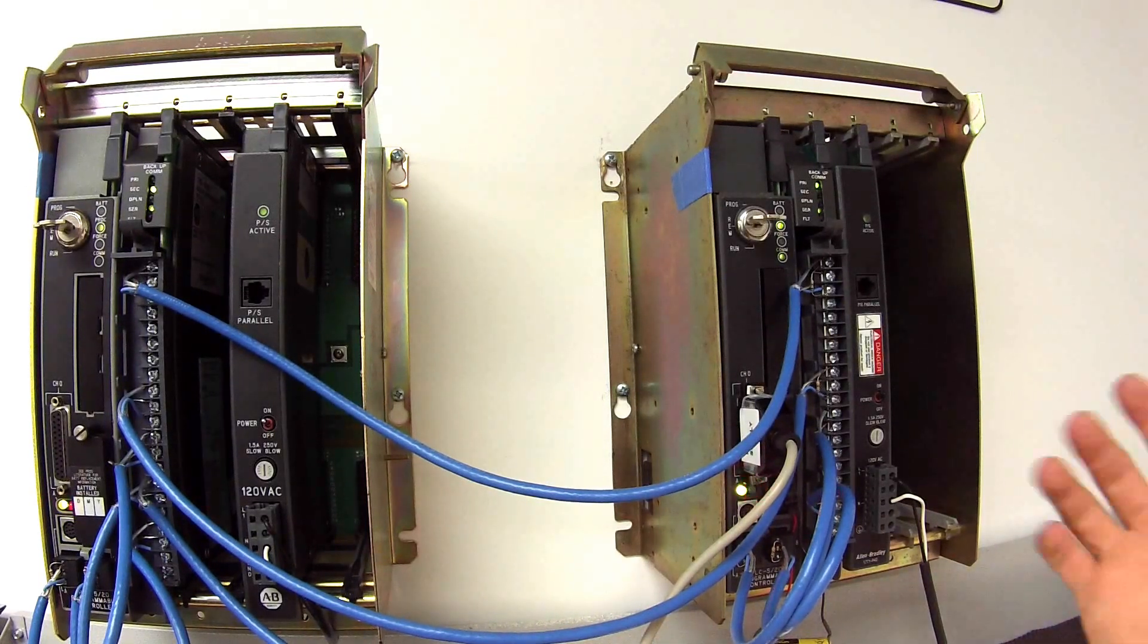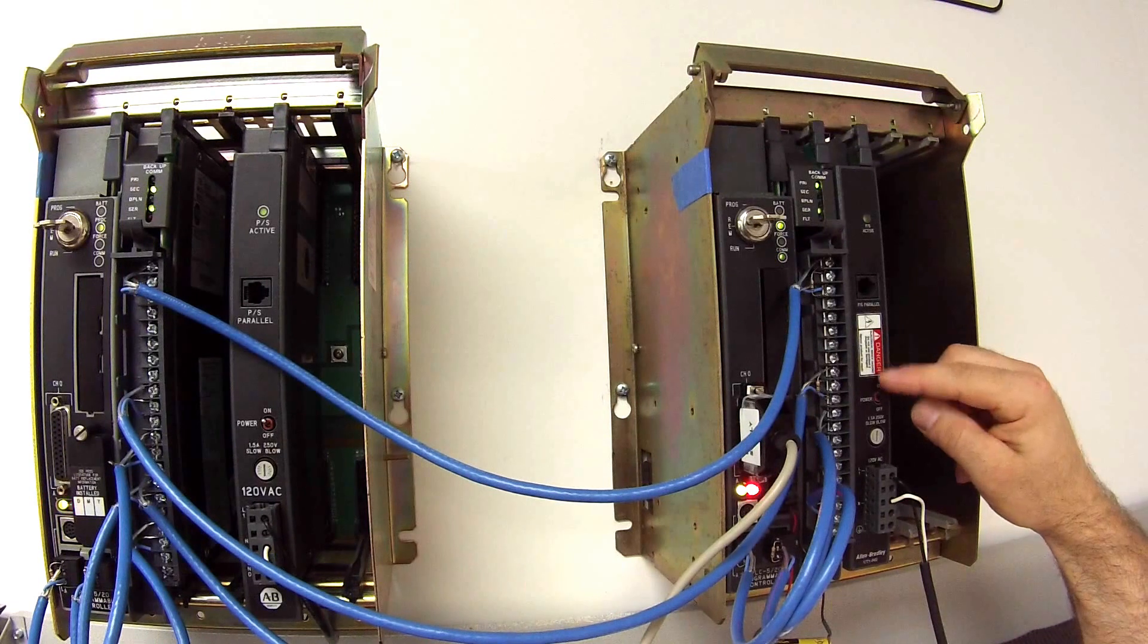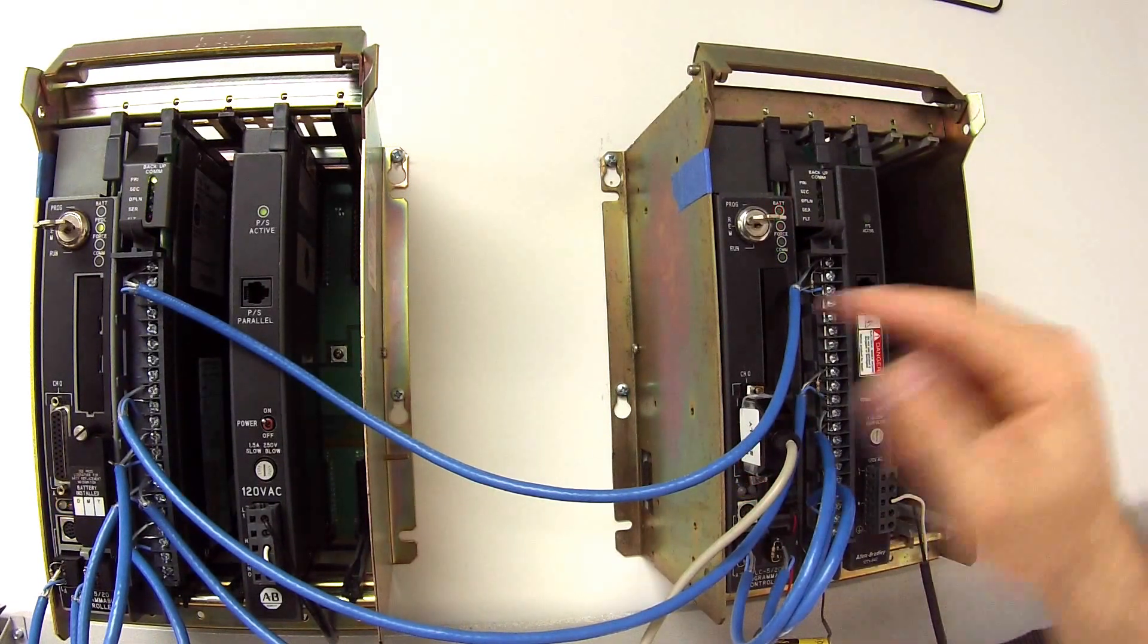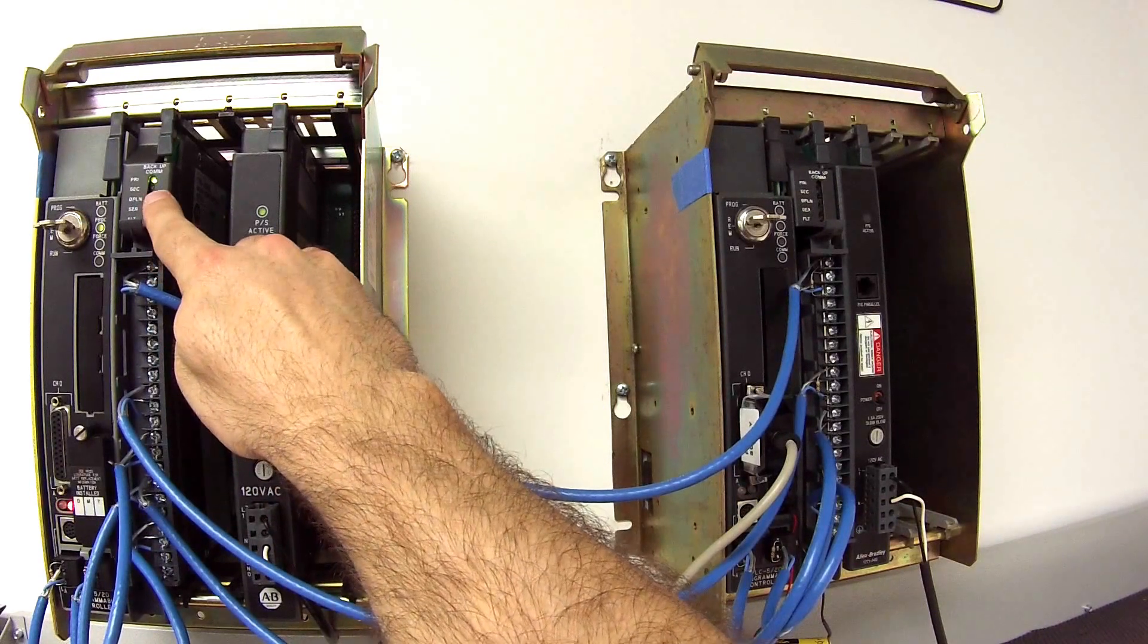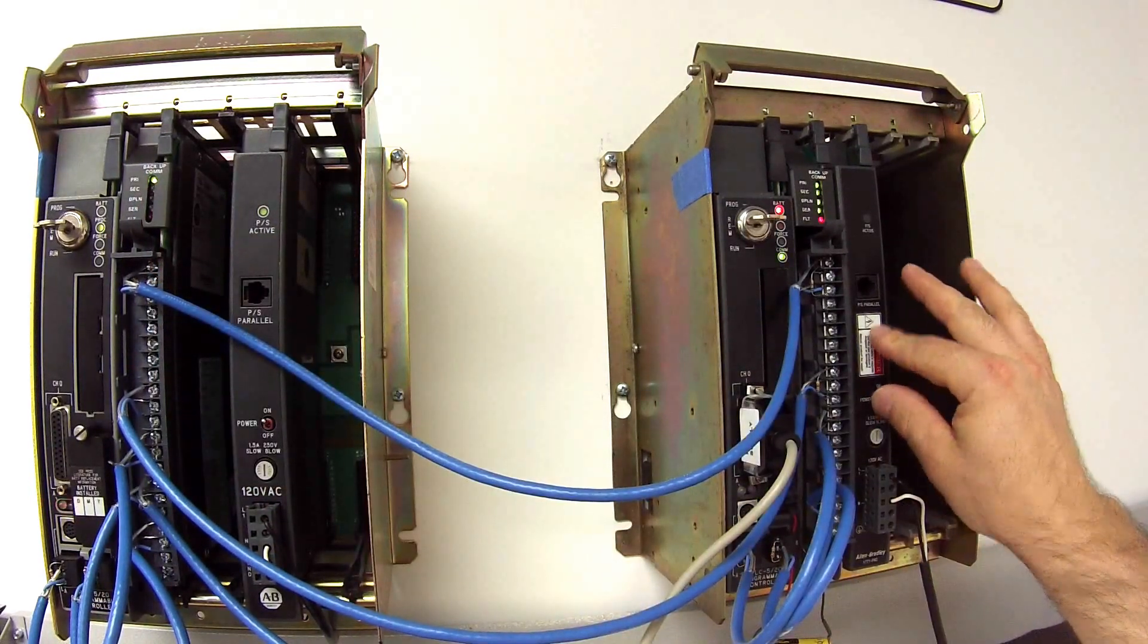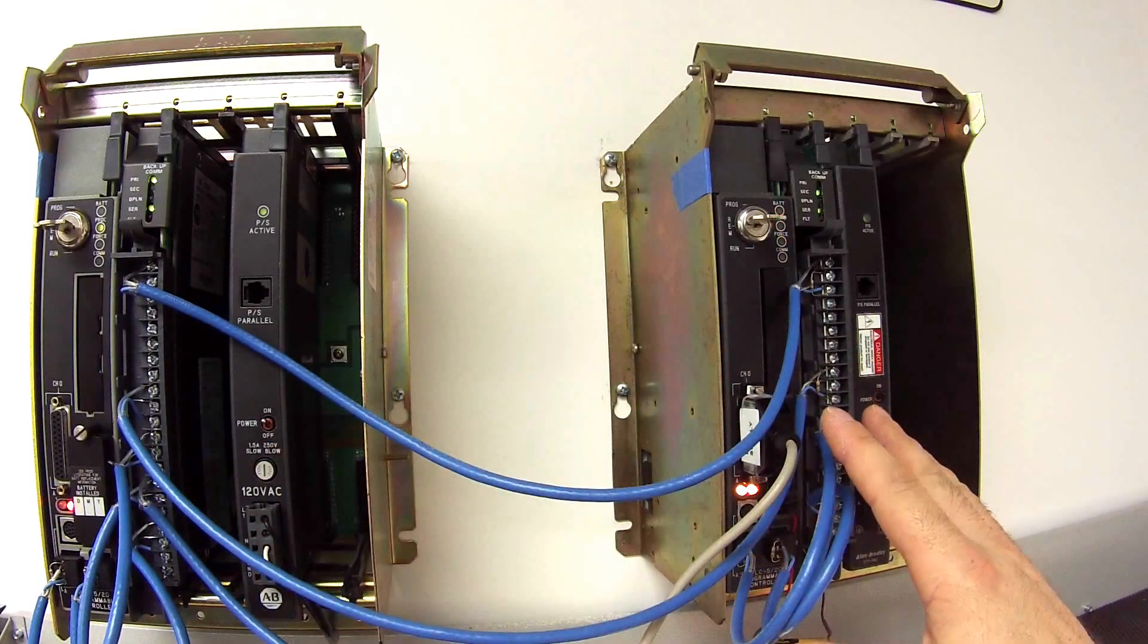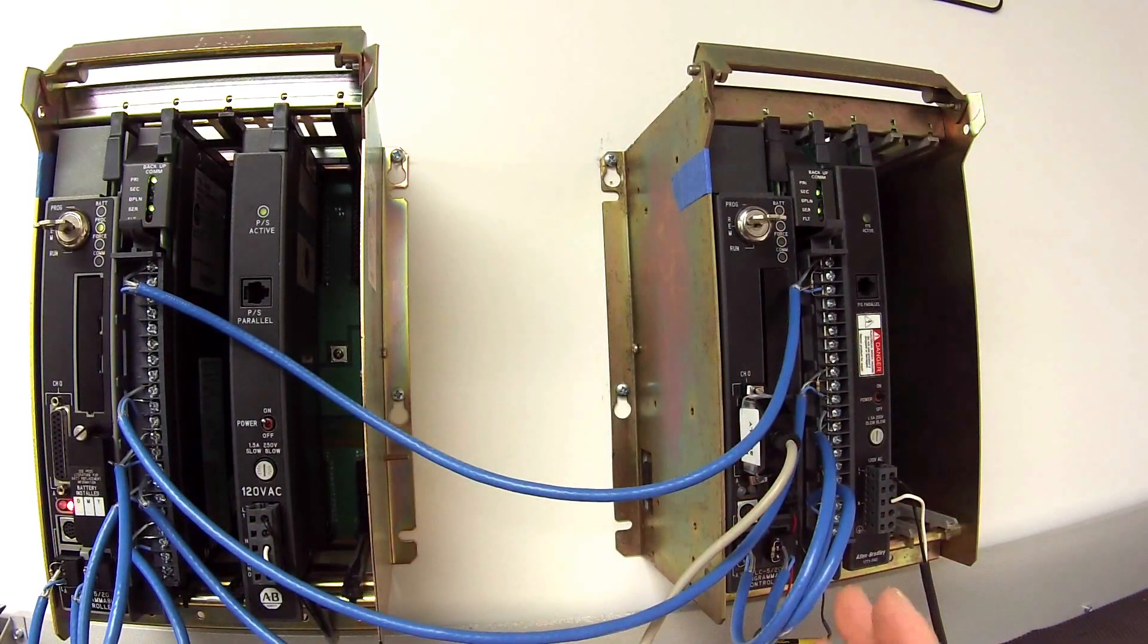And to even further the test, I'll simulate a power failure on this side by shutting this down now. And my rack on the left has jumped into primary. So, a little bit of back and forth there, but this is telling me that these two processors are communicating properly. They're doing what they're supposed to be doing when they're supposed to do it.